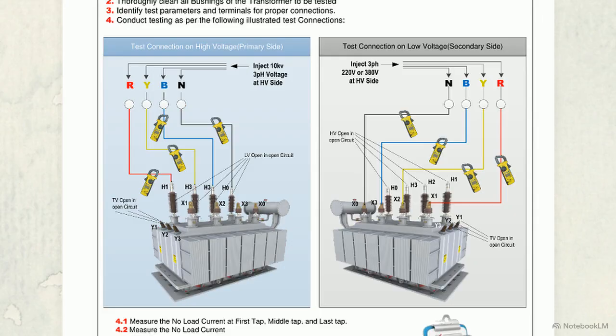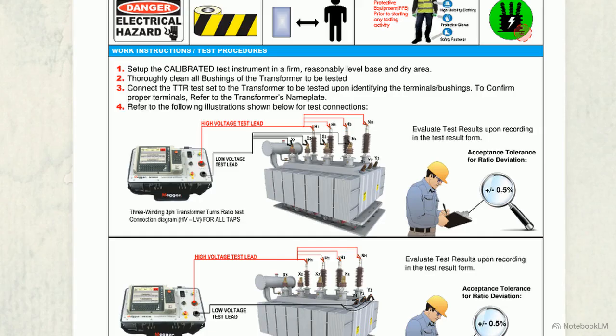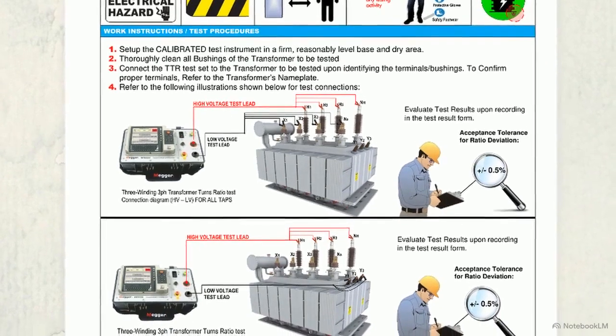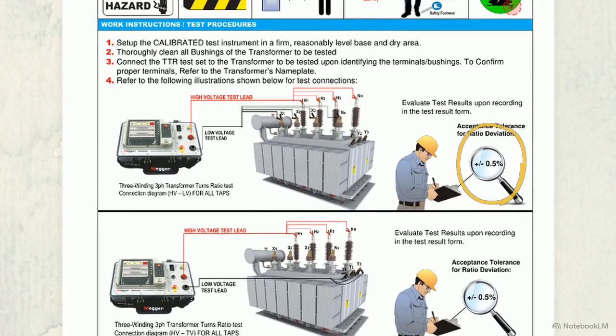This testing diagram details excitation-current testing, which verifies core symmetry. We apply a 10 kilovolt injection on the high voltage side, while keeping the low voltage side entirely open circuit to detect no-load core faults or shorted turns. This manual page shows the setup for the transformer turns ratio, or TTR test, mapping the connections across the 3-winding bushings. The goal is to verify phase angles and ensure the measured voltage ratio deviates no more than 0.5% from the nameplate rating.